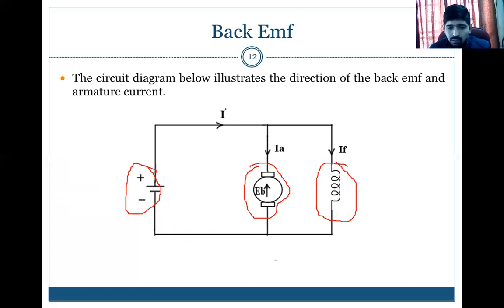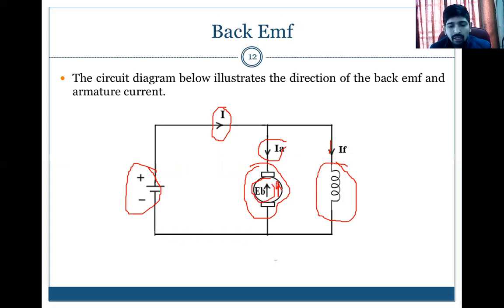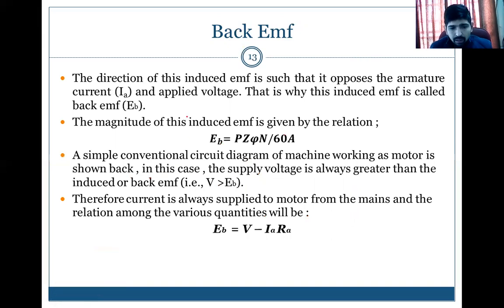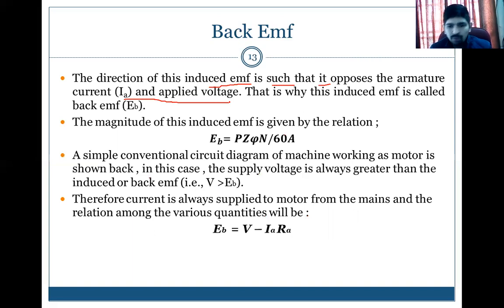DC supply is given to both — the field winding acts like a magnet producing flux. The total line current divides into armature current (IA) and field current. When armature current IA passes through the armature, an EMF is generated — that is back EMF (EB) — and its direction is upward, that is opposite to IA. The direction of this induced EMF opposes the armature current and the applied voltage. That is why this induced EMF is called back EMF.